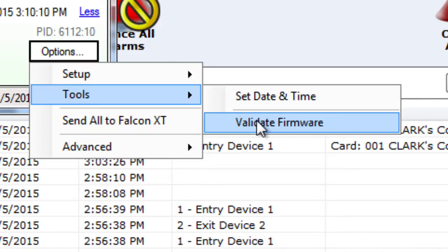There's no mechanism in this version of Logix Server to do a manual firmware update. Those have to be done through the bootloader now if you need to roll back for any reason. Going forward, let's say you're going from version 6.25 to 6.26, all you'd have to do is put the 6.26 in the firmware folder, come into the dashboard and click on Validate Firmware, and it would just start doing the update for you. So you don't have to mess around with anything there.